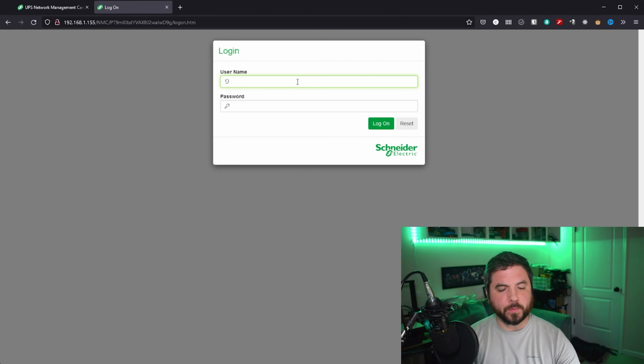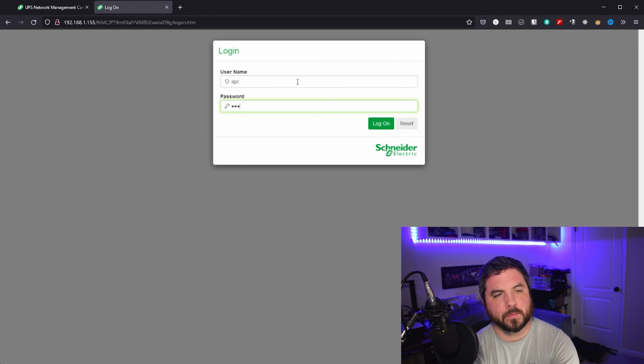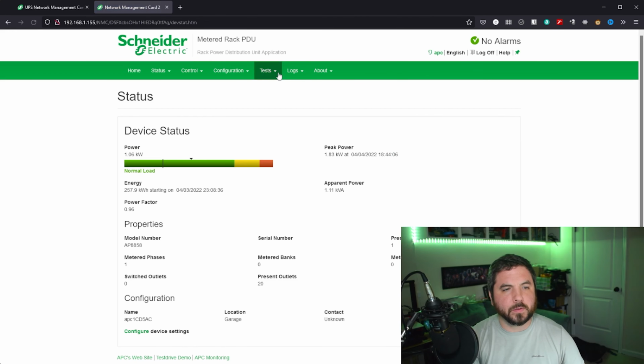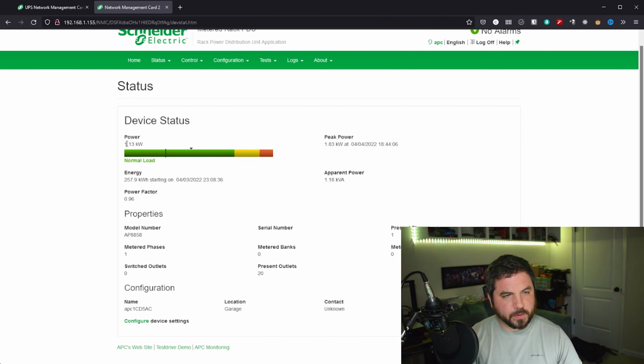Over here on the PDU, we have a little bit more information. It's that same APC user when you log in to your PDU. In this table, we have the current usage, and it's well within the normal load. I had a peak power usage on 4.4 at 1.83 kilowatts. I think that's when I had everything turned on, just doing a usage capacity test with everything in my rack turned on. I was not even hitting 3 kilowatts. So that's pretty good. This guy is rated for, I want to say 3,600 watts. 3,700 watts.